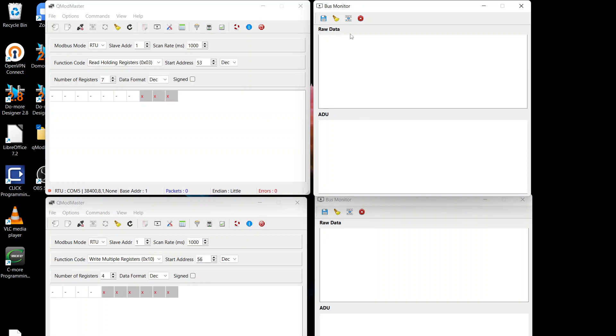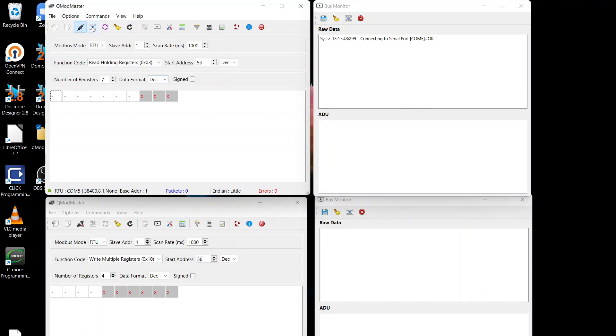So the top two windows here are for reading holding registers, the bottom two are for writing the holding registers. I've got this one set up to read the whole seven registers from 51 through to 57. That's that block for channel out 0 or channel out 1. If we do a read, I'll just connect to that.